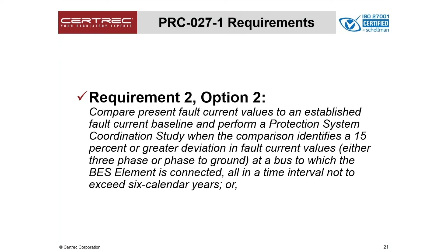Let me clarify that. So for the option 2 steps, as we said, you compare the fault currents to the identified baseline fault, our number being 15% that we're looking at. So if you're less than 15%, you do not have any other action. If you're greater than 15%, then you'll have to do the protection study. Again, if you find that, it cannot exceed the 6 years from the initial baseline to do the coordination study.